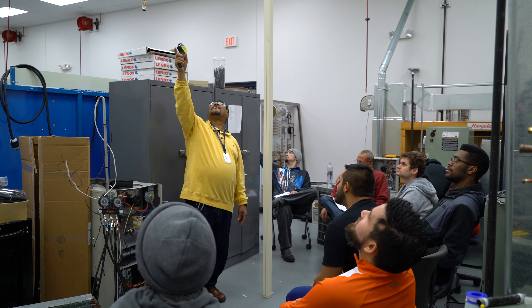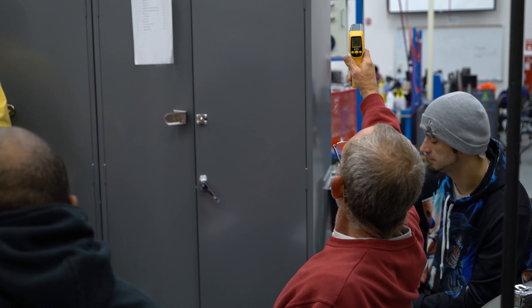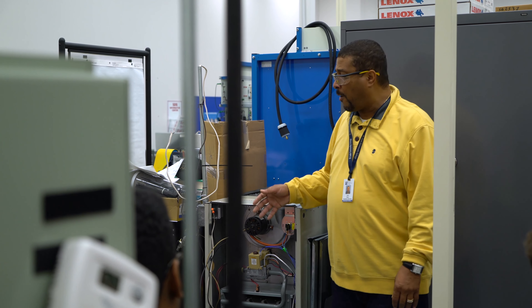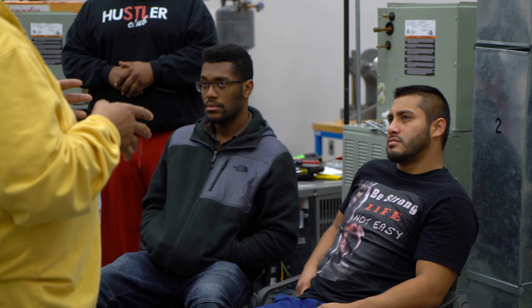The way I train my students, I train them in real-world applications such as troubleshooting the furnace — why the furnace does not come on, why it's not moving that air properly. If it's not going to move that air properly across the coil, it's going to freeze up.